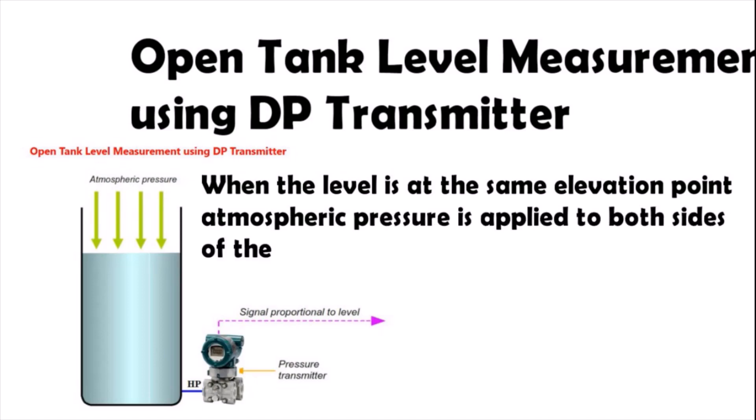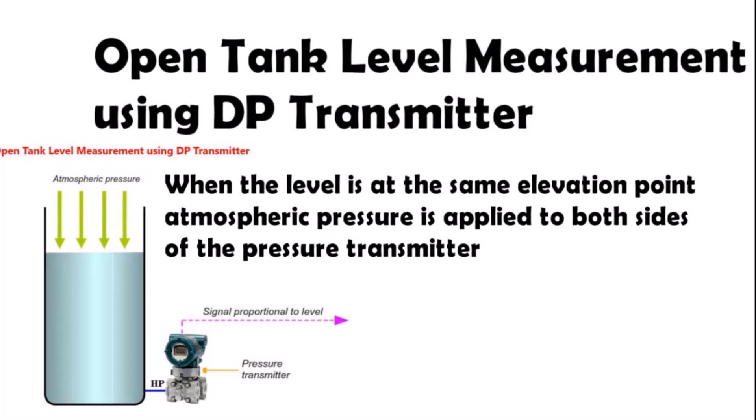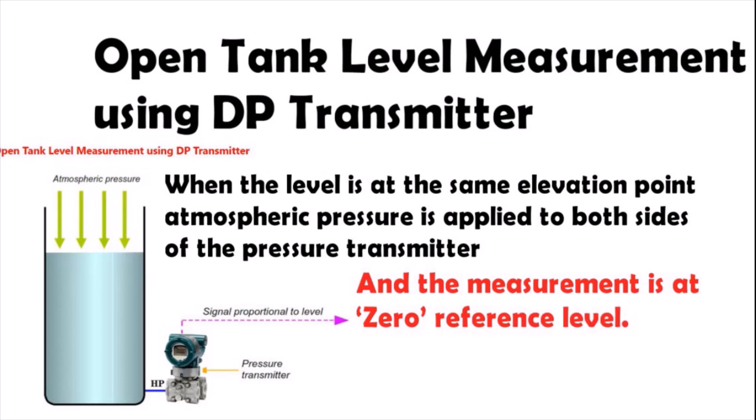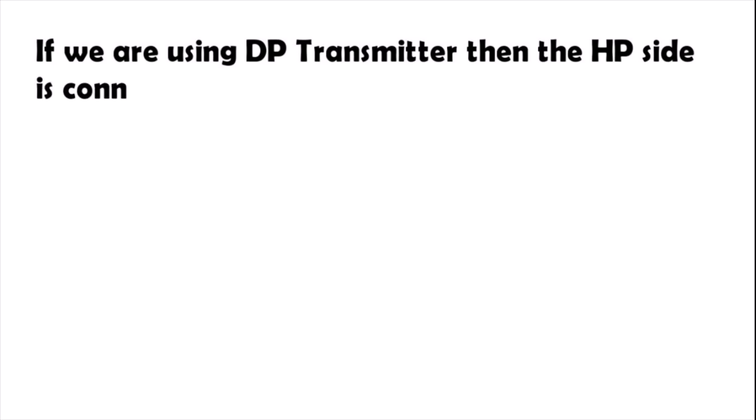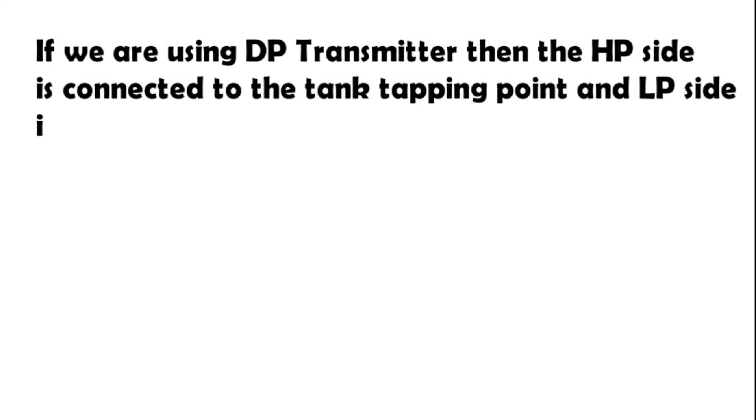is applied to both sides of the pressure transmitter and the measurement is at the zero reference level. If we are using DP transmitter, then the HP side is connected to the tank tapping point and LP side is vented to atmosphere.